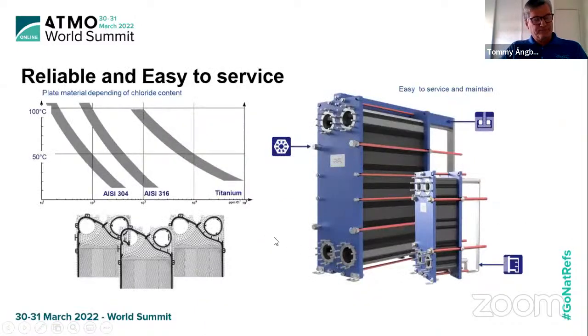But as I said, when you go to the cold side, we're having seawater, we have dirty water. It's important to select the right material of the plates or the heat surface. And here we have 3 standards. We use 304 or 316 when we have completely clean liquids. But if we have seawater, then titanium is the one to choose. And 316 could be for the intermediate or higher temperature duties.